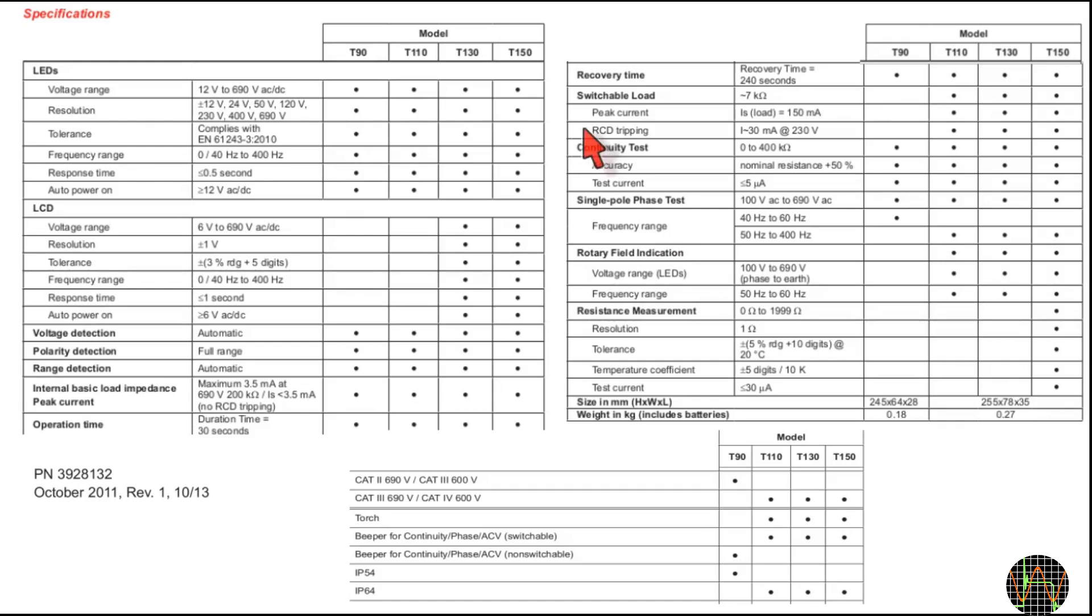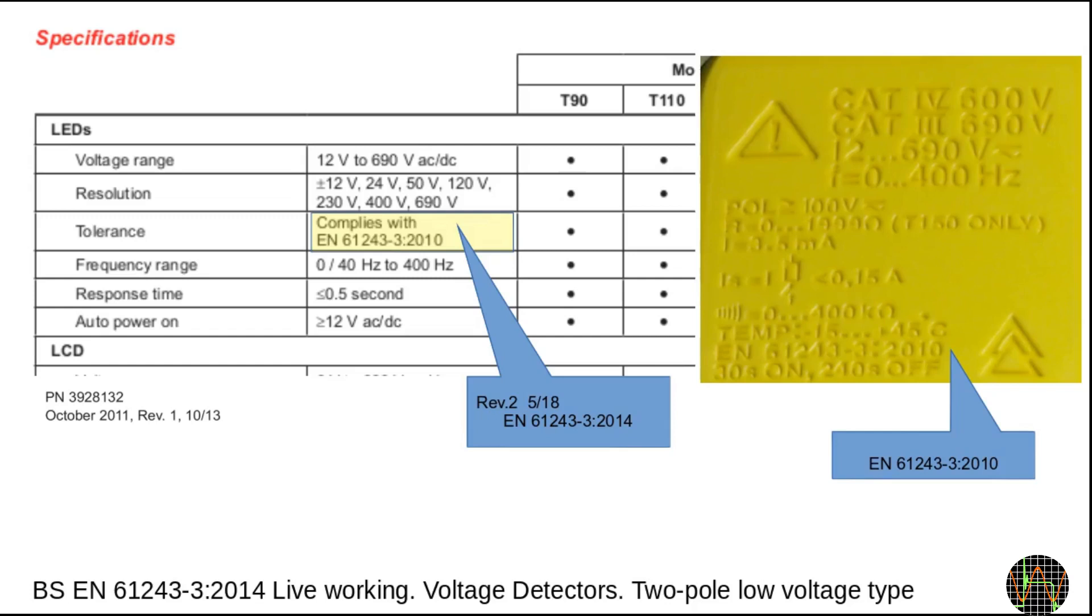An important feature of the T110 against the T90 is the capability to switch a load into the measurement circuit to trigger RCDs. The other differences between T90 and T110 are the better CAT rating and IP protection offered by the T110, the built-in torch which can come in handy, and being able to turn the beeper on and off, which at least for the T110 is quite loud.